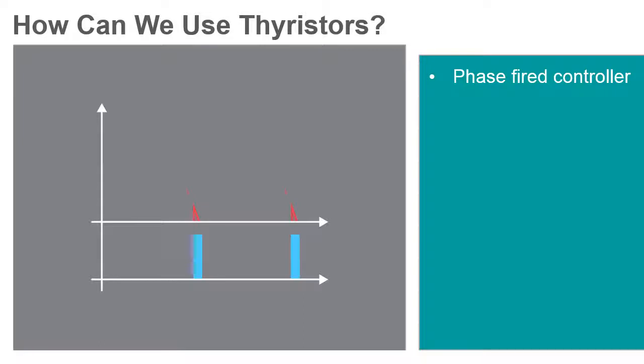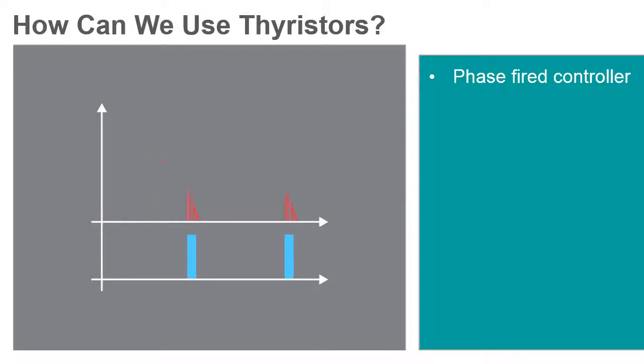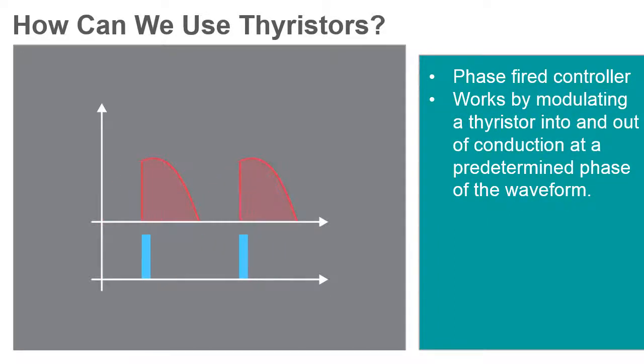Thyristors have a number of different power control uses. One such use is in phase-fired controllers. Phase control is a method of pulse width modulation applied to AC voltages. It works by modulating a thyristor into and out of conduction at a predetermined phase of the applied waveform.